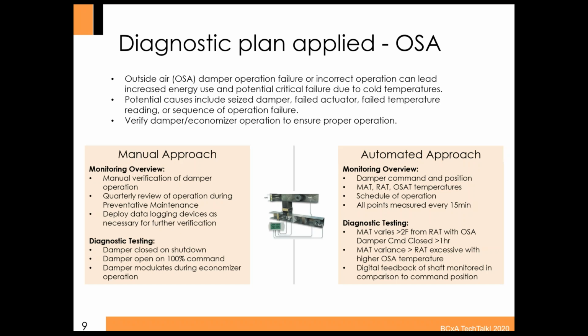Likewise, when the damper is commanded to 100%, you're doing a verification of the damper position, and that you're seeing that modulation during economizer control. So, through preventative maintenance and through a process, you're validating that damper, you're validating the performance of that system. When you see the automated approach, it's checking the same things, but the results are much different at that point. It's much more continuous, and it's more detailed in what it's able to evaluate.